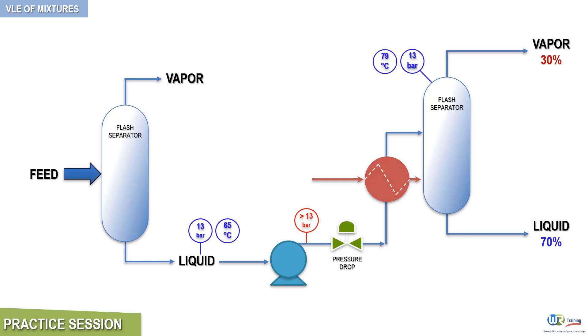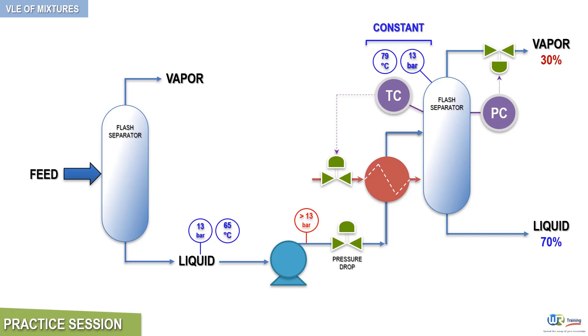In addition, we can improve this process arrangement by adding a basic process control system to it. Since the objective of the second flash separator is to yield a constant 30% vapor overhead, the operating temperature and pressure of the separator must be held constant. This can be achieved by adding two control loops: one loop will act on pressure and the other on temperature, as depicted here. The pressure control loop is based on the separator's overhead pressure.